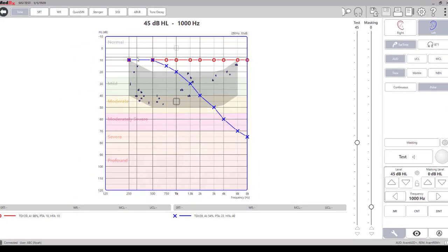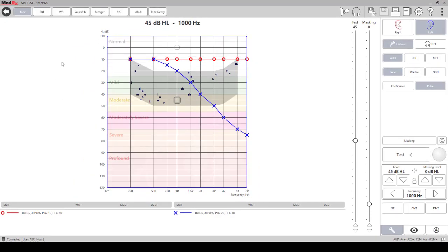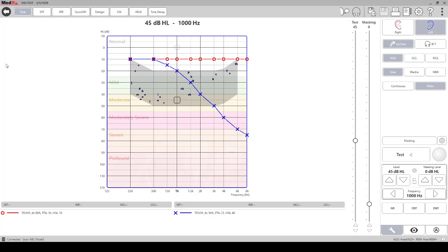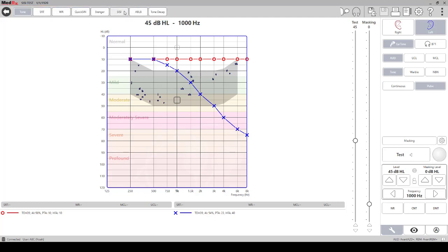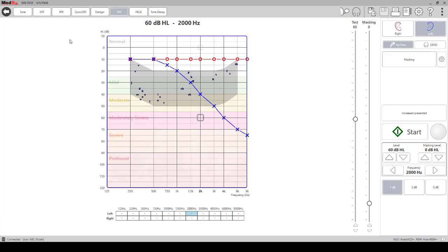This is your typical audiometry front screen where you're going to input the thresholds. You have transducers and everything else here on the right hand side that you would normally use to perform the regular air and bone conduction testing. On the top of the screen we have different tabs for different tests that are available. If we click on the tab for this test here we have the same audiogram that was shown on the front screen.